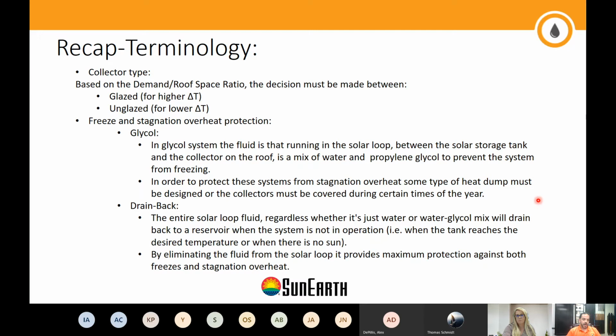So what we can do is use complete, manufactured solutions that are ready to go. Look at this example: a simple glycol system with an external heat exchanger for load and an external heat exchanger for supply, meaning the solar array is completely separated with one heat exchanger, and then a secondary heat exchanger runs between the solar heat exchanger and the potable water, creating an extra degree of protection.